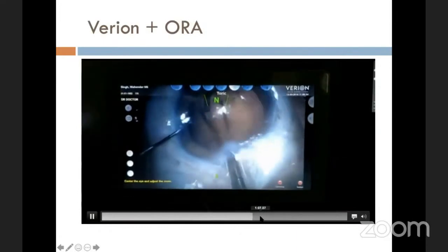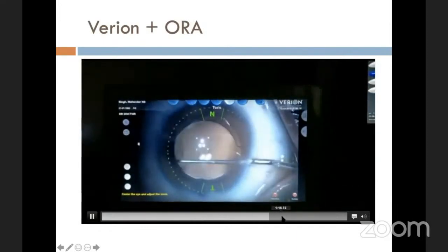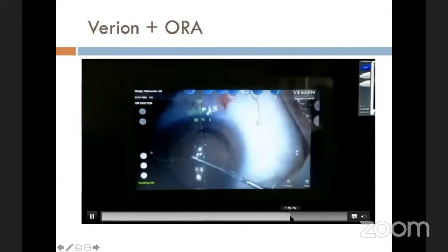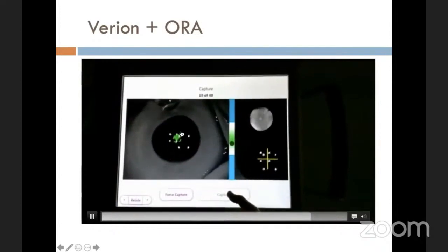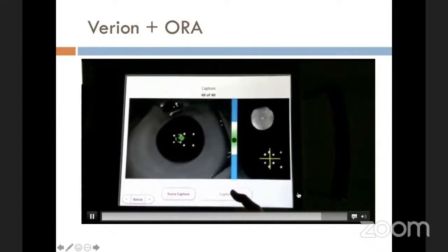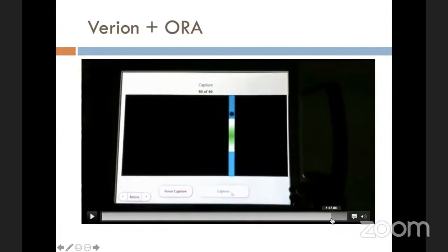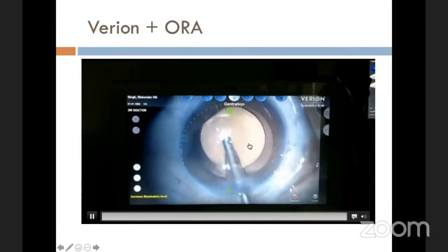So we change the lens to get more cylinder, and again align it onto the axis which is shown, and then also confirm it with the ORA. So this green thing has to come inside this green basket, and when that happens, then you know that you are completely focused. And again, the endpoint will be something like this, no rotation required. So we've confirmed on 2 instruments now.